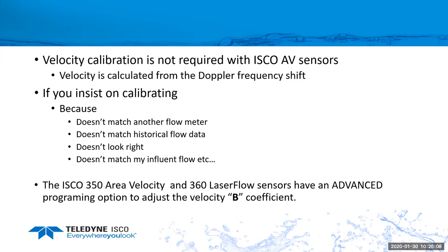There are some options. With the ISCO Signature 350 area velocity sensor and the laser flow sensor, in the advanced programming, we have a velocity coefficient. It's labeled under coefficient B. If you have an offset that you want to put in there, that is where we can enter that offset. Or afterwards in the FlowLink software, we can apply a coefficient to it to adjust the velocity and recalculate your flow rate.